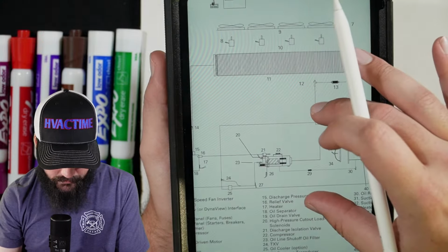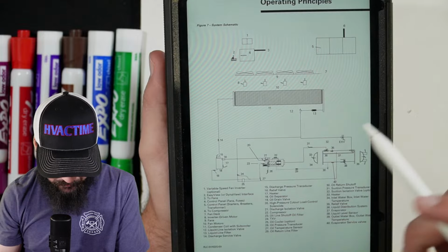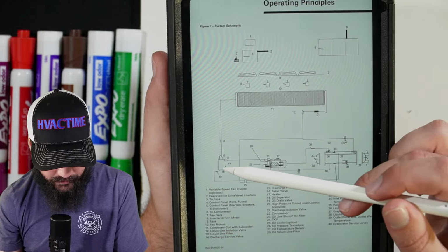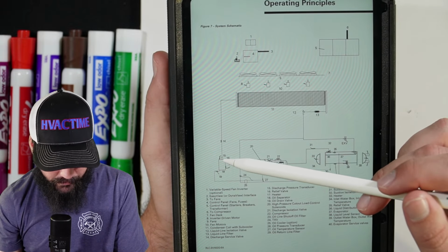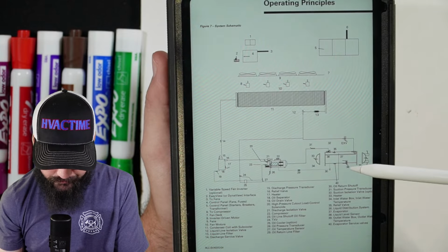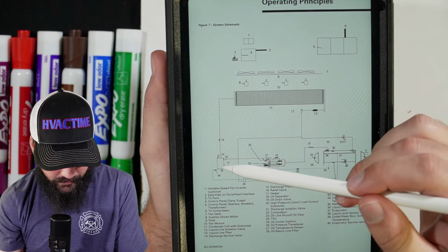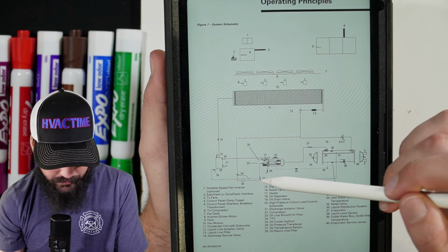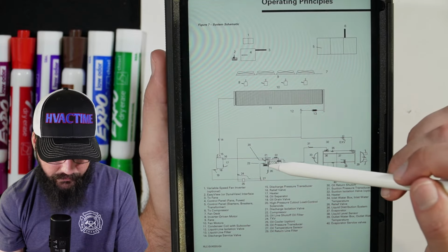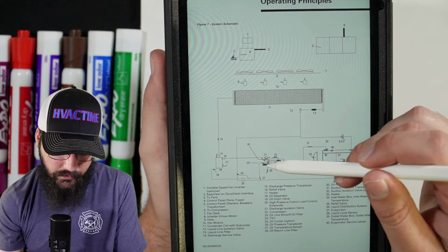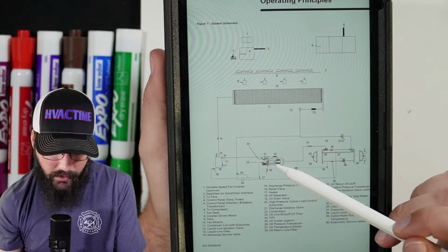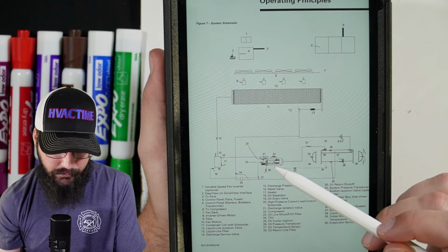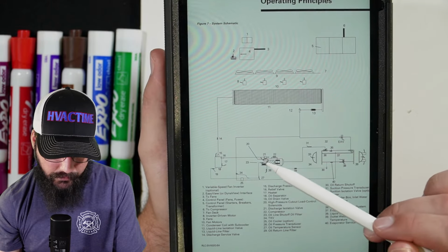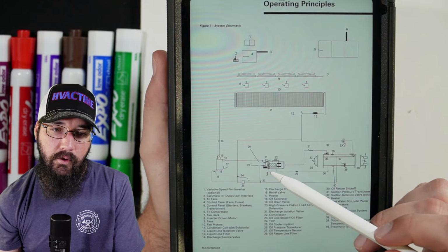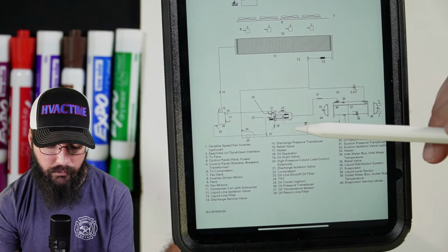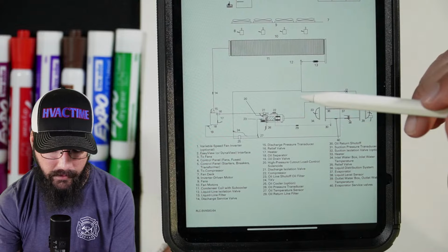But okay, so looking at RTAC, this is your basic refrigerant circuit. Here's our compressor. We come out the discharge into an oil separator. From the oil separator, discharge gas comes out and makes its way back to the condenser, and at the bottom of the oil separator we have our oil return line that feeds into our compressor oil filter, which is all internal. And then the oil cycles through. The motor and the bearings on these compressors are on the low pressure side of the refrigerant circuit, and the oil feed itself is on the high pressure side. That's how we're able to maintain oil flow with no pump on these machines. We're using differential pressure to go from one side to the other for flow.